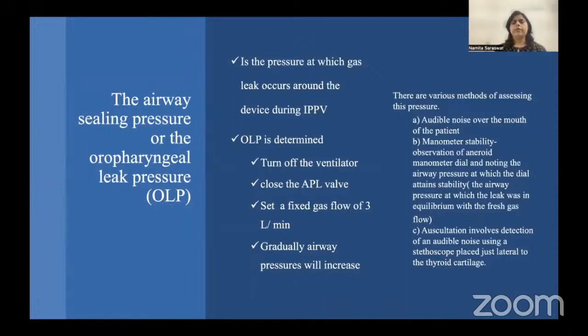After connecting the device to the circuit, turn off the ventilator and close the APL valve. Set a fixed gas flow at 3 liters per minute, and you will observe on the ventilatory parameters that airway pressures gradually keep increasing. Then how will you measure it? There are 3 methods with which you can assess the pressure.